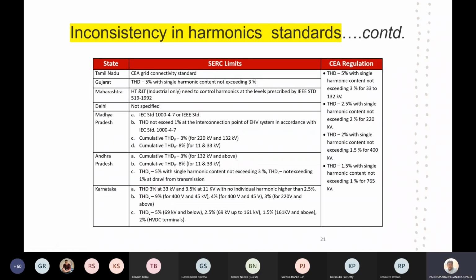IEEE standards are different from Indian standards because Indian standards are not constant. Gujarat state says 5% with single harmonic content not exceeding 3%. Likewise, each state has THD values that are not uniform. If you observe Andhra Pradesh, cumulative THD should be 3%, whereas here in Karnataka it should be around 4%, and 9%. Likewise, a uniform pattern is not observed in the various states.